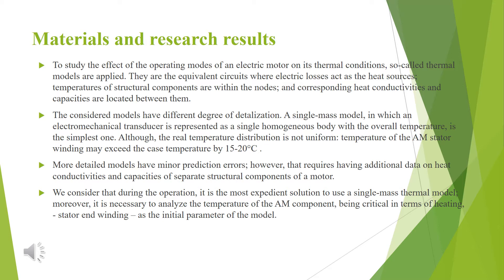The considered models have different degrees of detail. A single-mass model, in which an electromechanical transducer is represented as a single homogeneous body with an overall temperature, is the simplest one. Although the real temperature distribution is not uniform — the temperature of the asynchronous motor stator winding may exceed the case temperature by 15–20 degrees — more detailed models have minor prediction errors. However, they require additional data on heat conductivities and capacities of separate structural components of the motor.